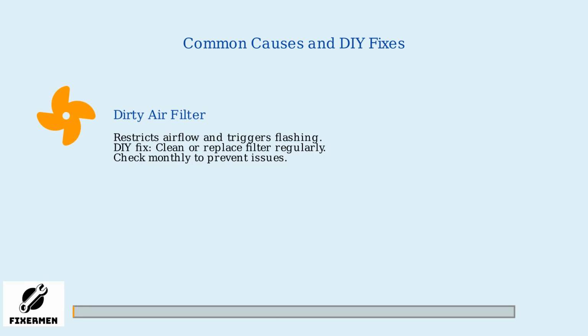A dirty air filter is another common issue that can cause flashing lights. When the filter becomes clogged with dust and debris, it restricts airflow through the system, making the AC work harder. Fortunately, this is an easy DIY fix. Simply clean or replace the filter every 1 to 3 months depending on usage. Blocked vents or obstructions around your outdoor AC unit can also trigger flashing lights. Debris like leaves, dirt, or overgrown plants can block airflow, causing the system to overheat or strain. This is another simple DIY fix. Regularly clear any obstructions and maintain proper clearance around the unit.